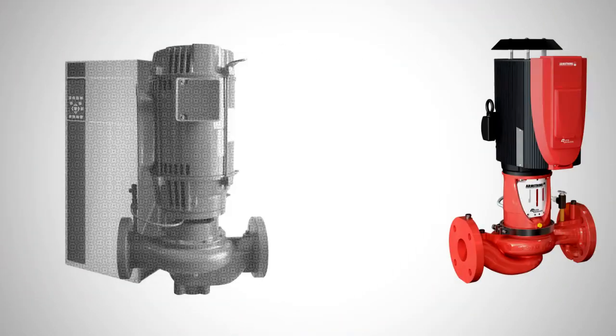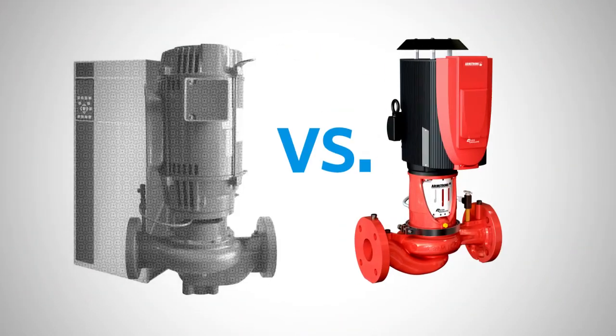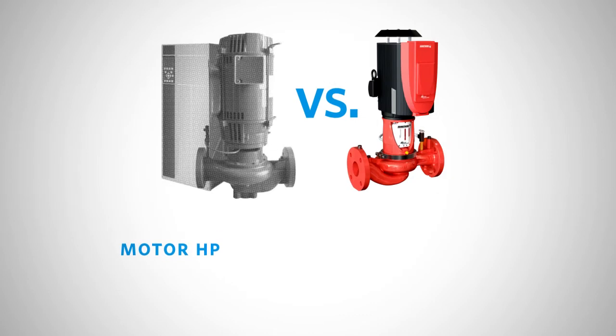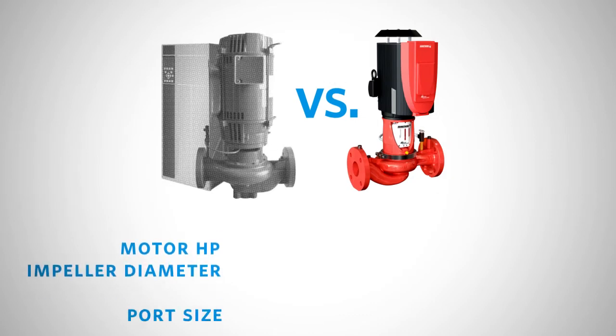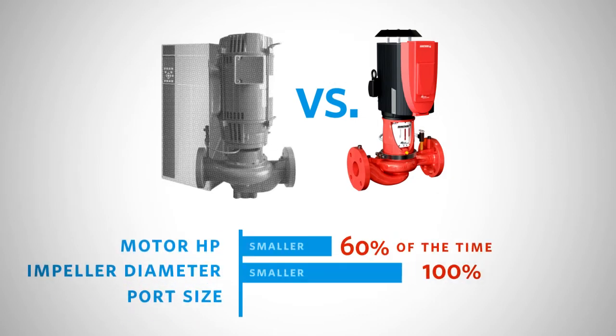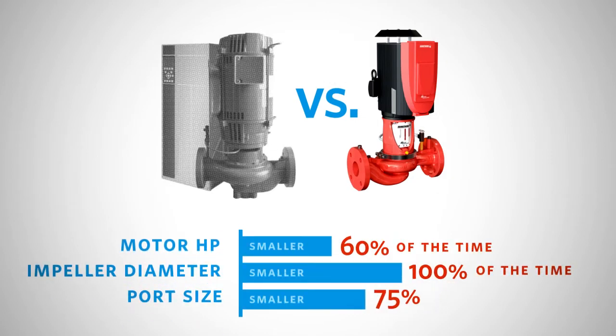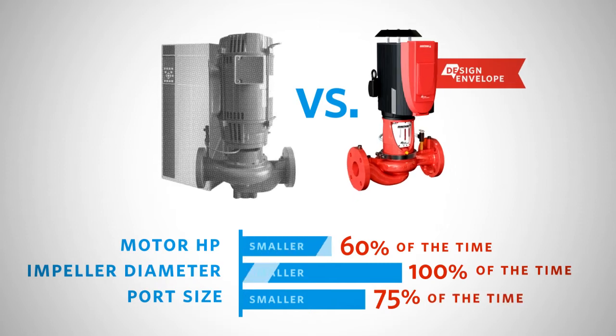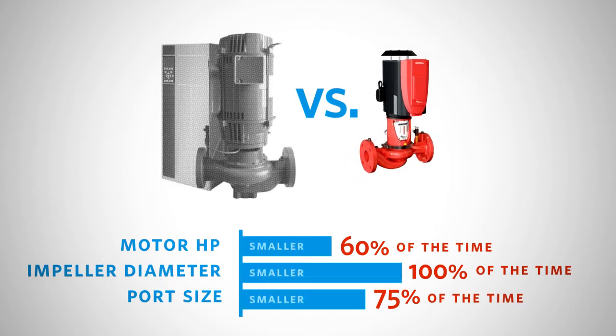In 60% of installations in the 1/3 to 10 horsepower range, the pressure and flow requirements of the system can be served with a combination of design envelope pump and a motor that is one size smaller.